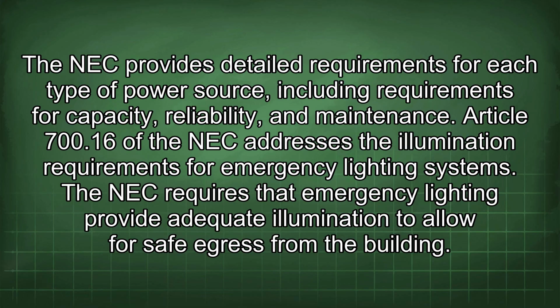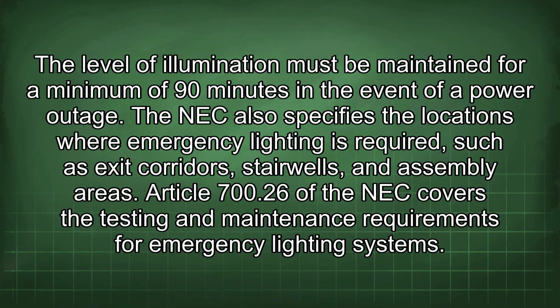Article 700.16 of the NEC addresses the illumination requirements for emergency lighting systems. The NEC requires that emergency lighting provide adequate illumination to allow for safe egress from the building. The level of illumination must be maintained for a minimum of 90 minutes in the event of a power outage. The NEC also specifies the locations where emergency lighting is required, such as exit corridors, stairwells, and assembly areas.